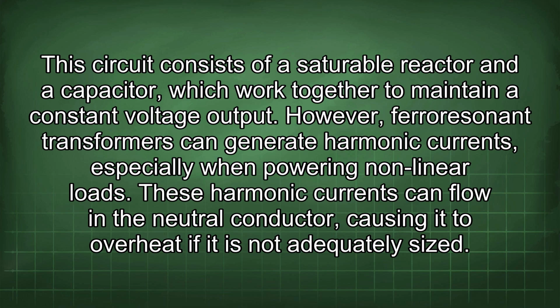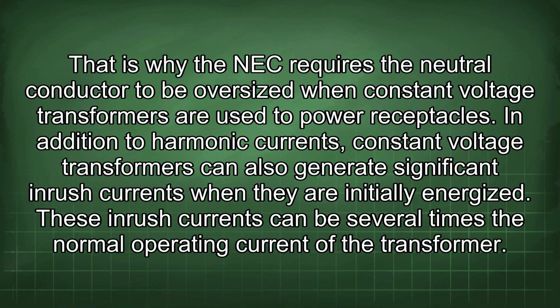However, ferroresonant transformers can generate harmonic currents, especially when powering nonlinear loads. These harmonic currents can flow in the neutral conductor, causing it to overheat if it is not adequately sized. That is why the NEC requires the neutral conductor to be oversized when constant voltage transformers are used to power receptacles.